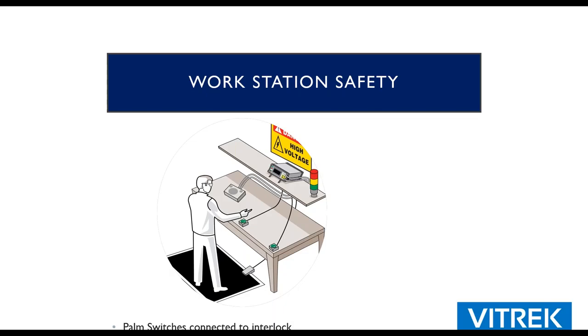So the first one is all of our testers have an interlock, and what that interlock does is it's basically just looking for a contact closure on the DIO port, and you can connect that to a switch. It could be a micro switch, it could be a light curtain. It's not picky about what kind of switch it is, but the whole idea is that you use that switch in an intelligent way to shut the tester down if it opens up during the test.